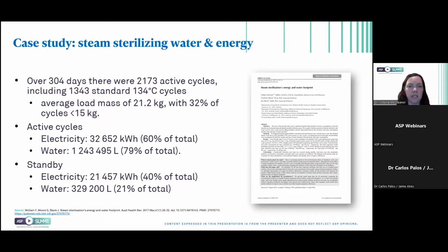The water consumption was about 79% of the total water and energy consumption over the 304 days, which meant that when the sterilizers were on standby, the electricity consumption just from standby accounted for about 40% of total consumption. Similarly, 21% of the water usage of these sterilizers was attributable just to those machines being on standby mode. So this research team found they could potentially save a lot of energy, electricity and water if they figured out a way of not having the sterilizers on standby for so long.